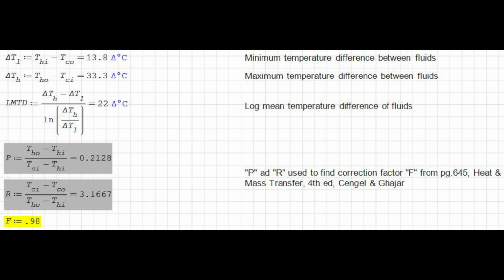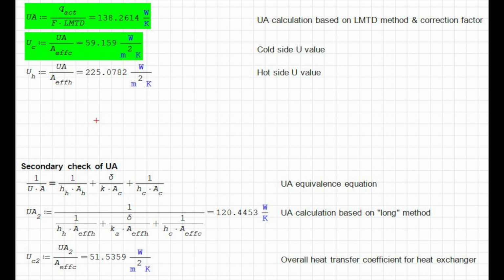Then we put in the UA value as the actual Q out, divided by the LMTD times F, and that gives us a UA value of 138.2614 watts per Kelvin. Then you divide by the effective cross-sectional, or effective surface area of the cold fluid, to get the cold fluid U value, which comes out to almost 60.